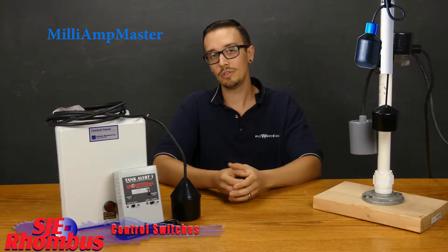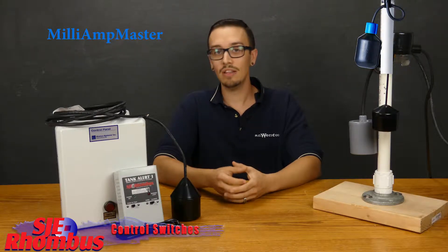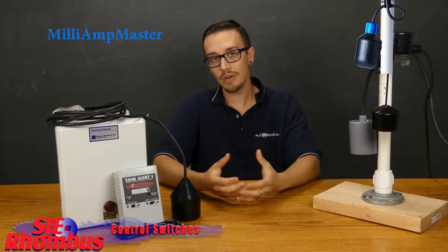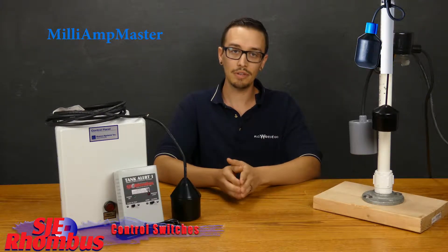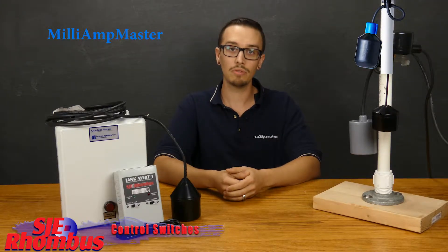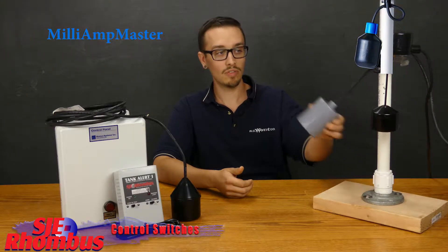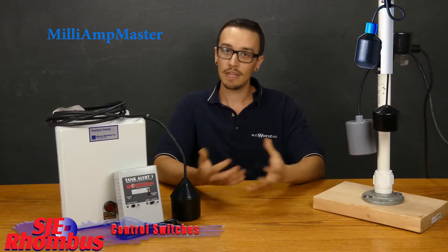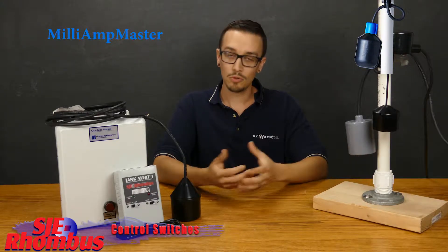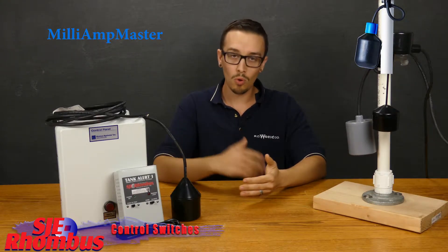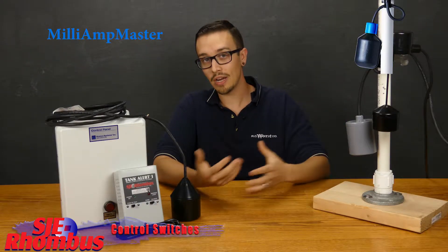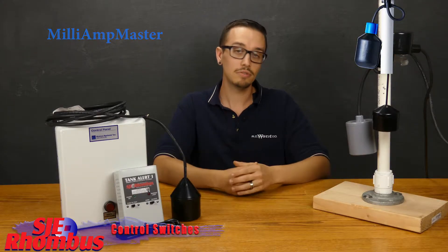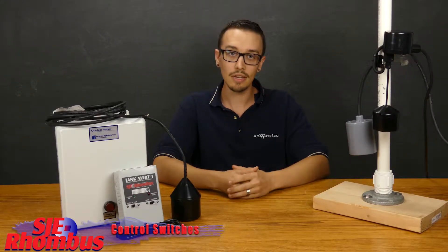The nice thing about those switches is they're also available in a wide angle configuration, so they can be ordered in narrow angle or wide angle if you need to accomplish more of a cycle with like a traditional pump switch where you've got a lot of swing going on. That's what your wide angle control switch is going to do for you. It's going to give you more mobility of that switch so you're able to achieve a longer cycle. Since pump switches are also rated for intrinsically safe applications, it's a great choice and I think it's definitely needed in the marketplace.